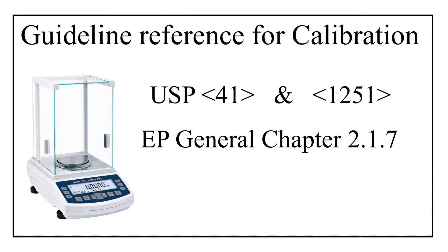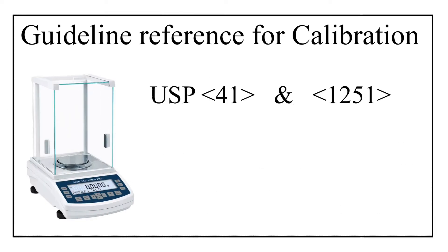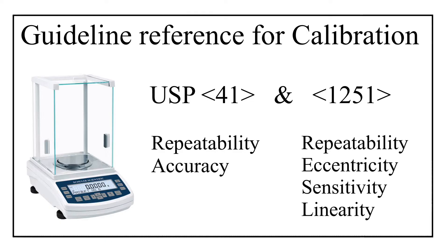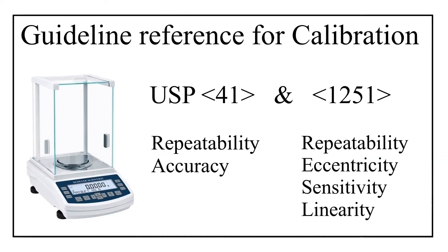If you read USP general chapter number 41 and 1251, you will find that some calibration parameters are covered in chapter 41 and others in chapter 1251. Specifically, repeatability and accuracy are given in general chapter 41, whereas sensitivity, linearity, eccentricity, and repeatability are covered in general chapter 1251. Note that the repeatability test appears in both general chapters.